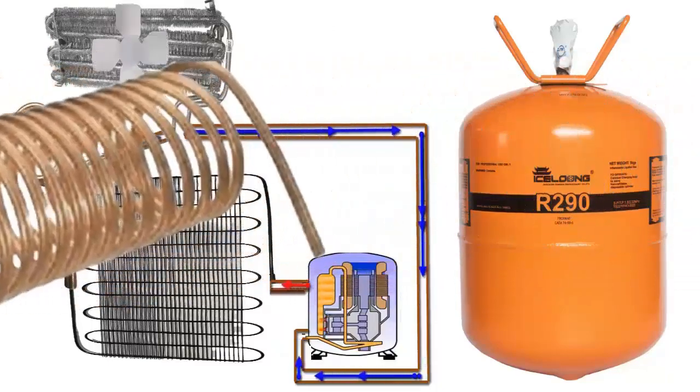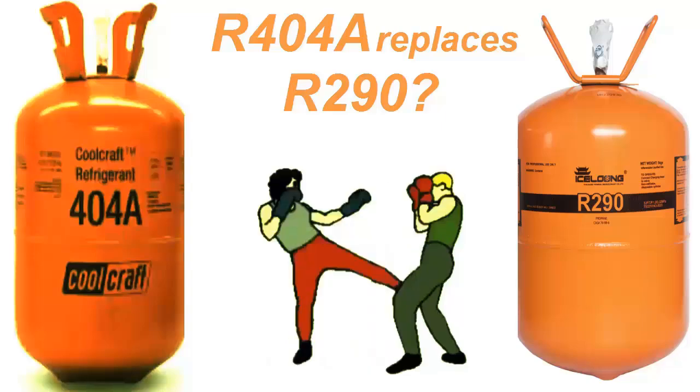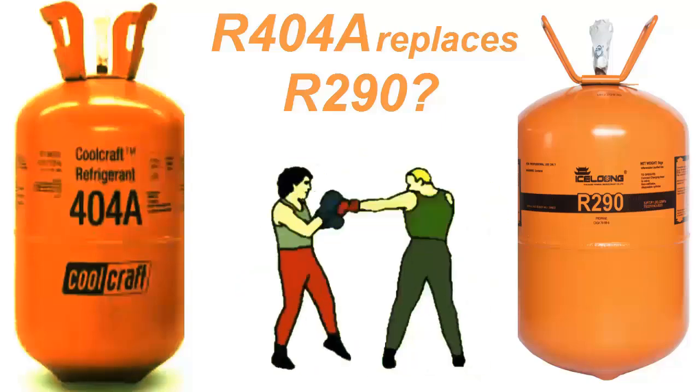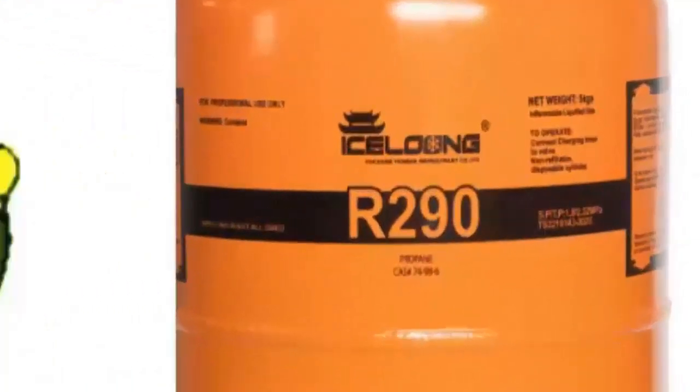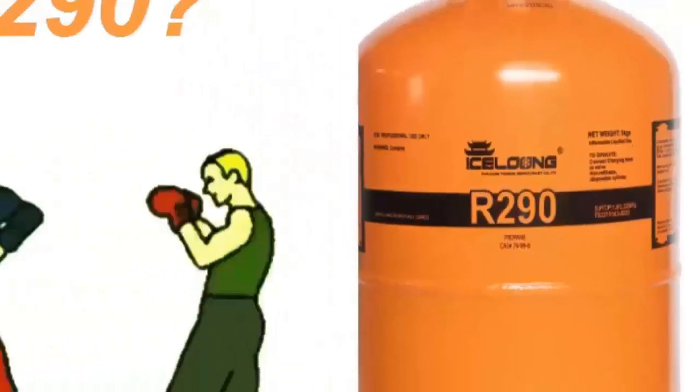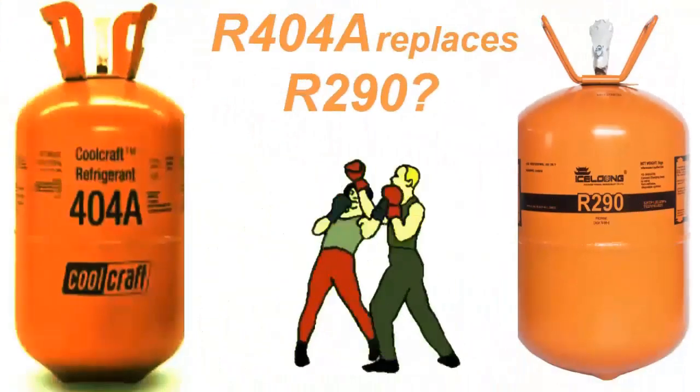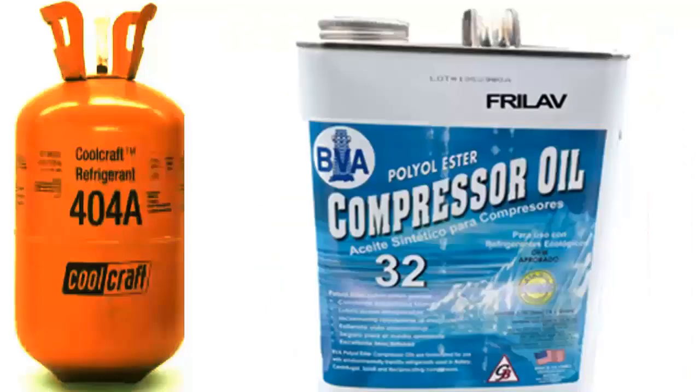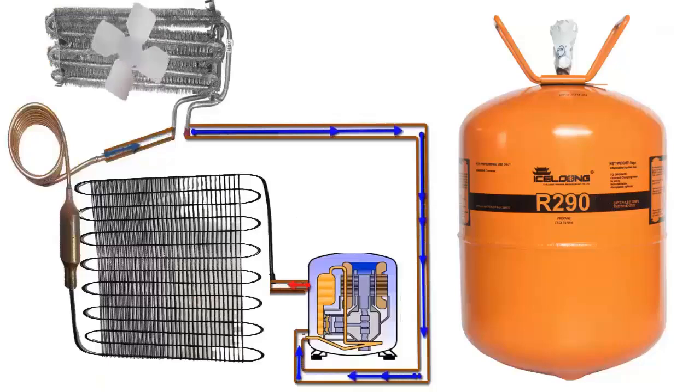6. Oil compatibility. R290 can work with several types of oil, while R404A strictly requires POE, polyol ester, oil. If the gas is changed without replacing the oil, this can damage the compressor and affect the system's operation.